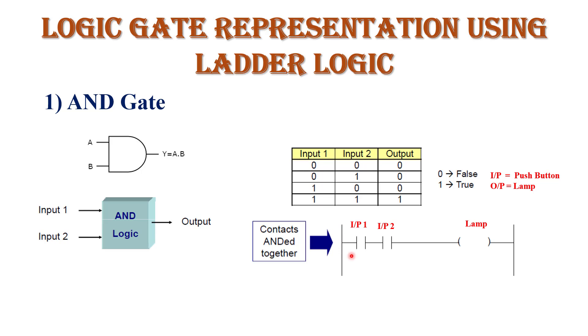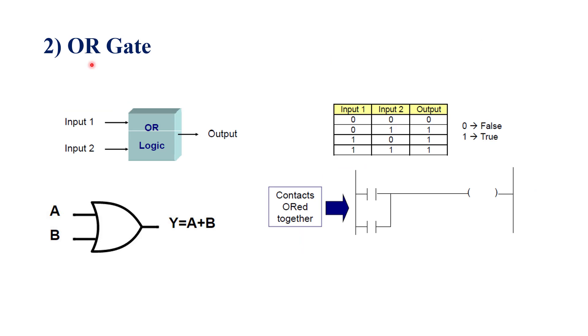Here we represent the AND logic gate using ladder logic diagram. The two vertical lines represent the power supply, and the horizontal line is the rung. For an AND gate, we connect two inputs — input one and input two — in series, and the output is also connected in series on the right-hand side. For input we use push buttons and for output we use a lamp. When both inputs are turned on, the output gets energized; if any one input is off, the output is de-energized.